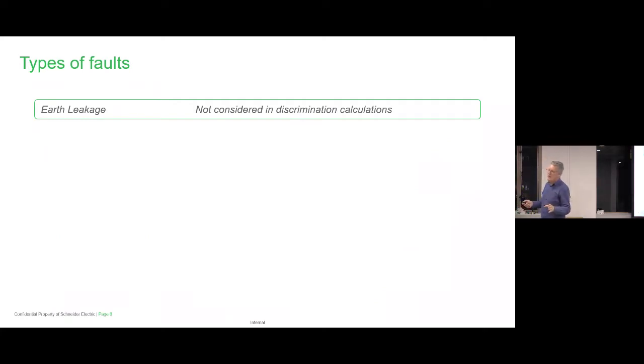We don't advocate as a company, even though we have earth leakage capability in our main breakers, ACBs, putting it in that area. Why? Because you don't put it in the sub-distribution and the final distribution. If you're not doing that, you're opening yourself up to nuisance tripping, a real problem. So if you want earth leakage in, absolutely do it at final distribution, but beyond that, make sure they're closed networks, okay? If they're not closed networks where you can control it, then I wouldn't bother.